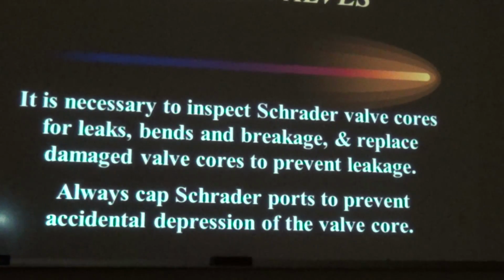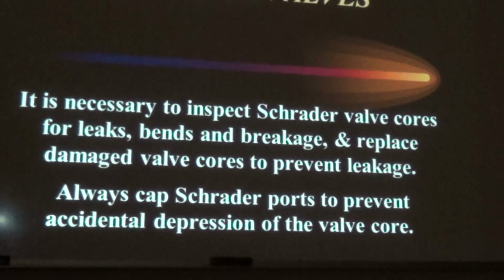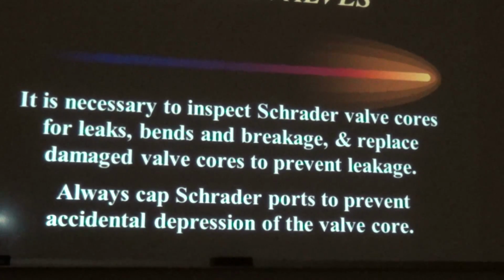When you're working with type 1 equipment, you're going to have to inspect Schrader valve cores, because these are going to be the main means of recovering refrigerant and adding refrigerant to a system, these Schrader cores.